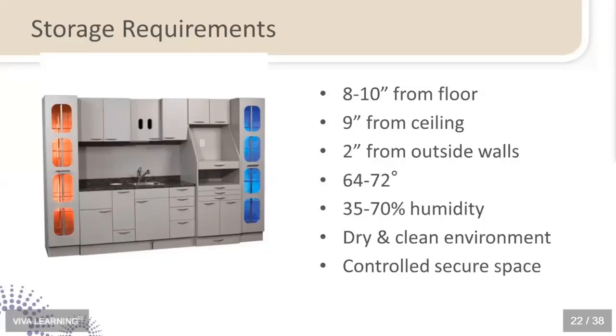Should there ever be a flood, you want to make sure your packages are not exposed. It has to be at least 9 inches from the ceiling, and there has to be a 2-inch space from the outside walls of the building. We have to maintain basically room temperature, 64 to 72 degrees, with 72 as the max, and a maximum of 70% humidity. A lot of that temperature and humidity requirement has to do with the impact it will have over time on the materials of your sterilized products.